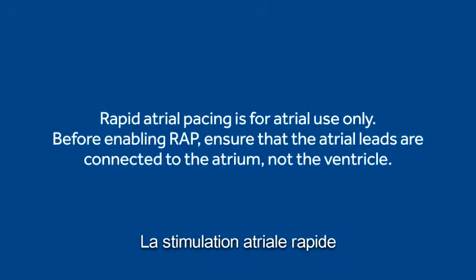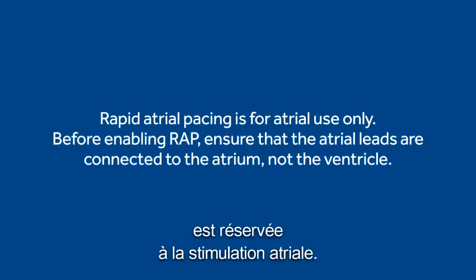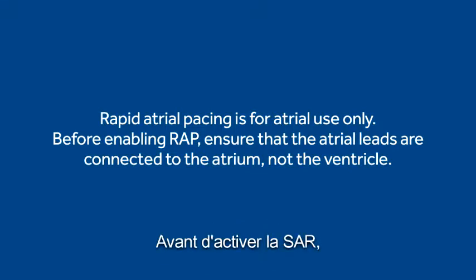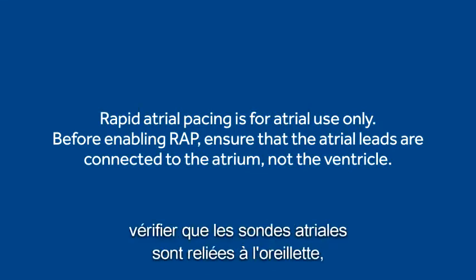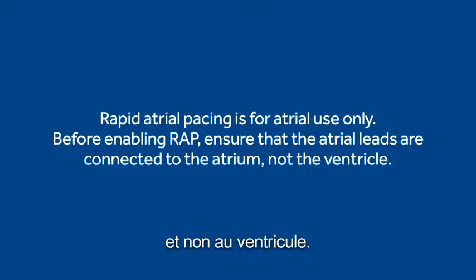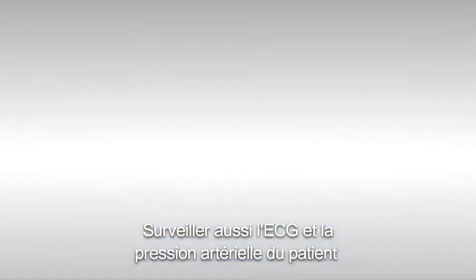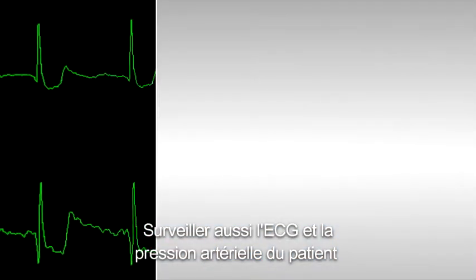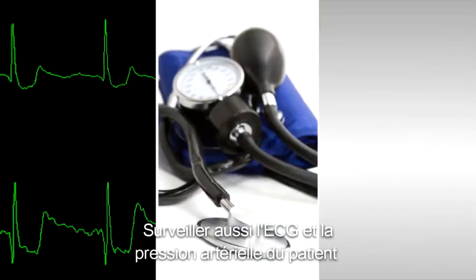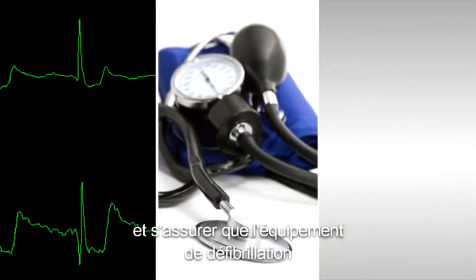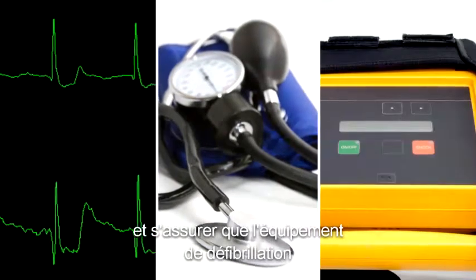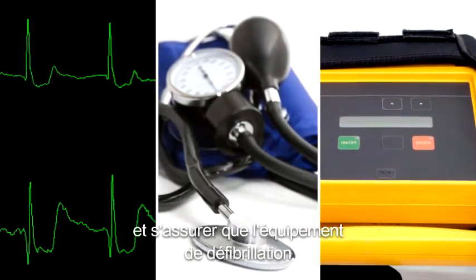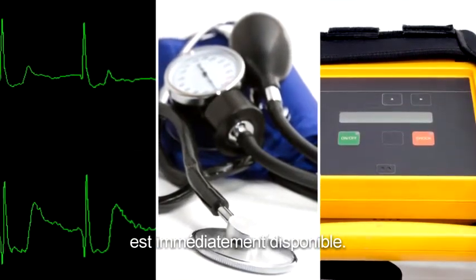Rapid atrial pacing is for atrial use only. Before enabling RAP, ensure that the atrial leads are connected to the atrium, not the ventricle. Also, monitor the patient's ECG and blood pressure and ensure that defibrillation equipment is immediately available.